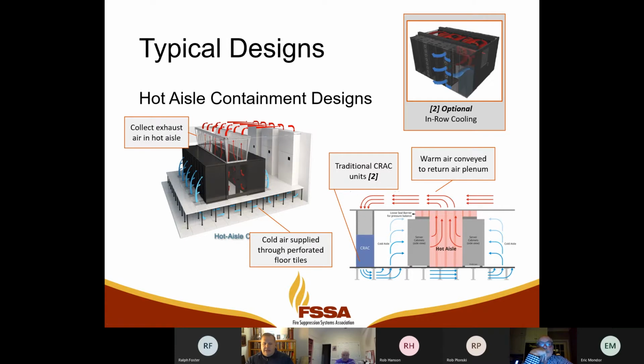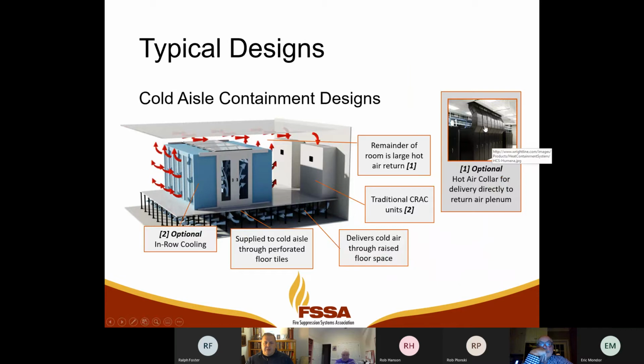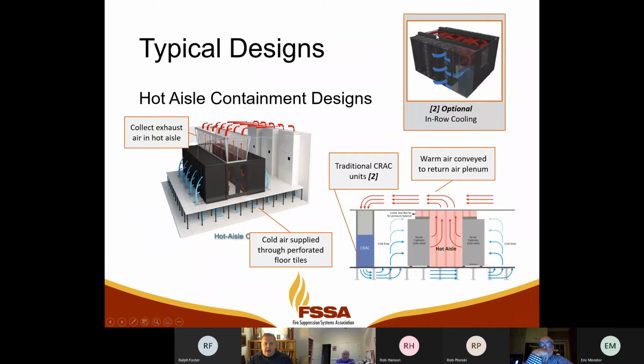There were two variants, and you'll sometimes see these in data centers. These are hot air chimneys. This is sort of a form of hot aisle containment. It's just an individual duct, more or less, from a rack to take that hot air up and out into the ceiling space. You'll see in-row cooling. It's a lot framed just like that cold aisle, with a door on each end and a roof. But then there's a cooling unit like a CRAC unit right there, taking up the space of one of the racks, and it cools air and blows cold air out, and it's drawn back in by the fan and by the little fans inside of the servers. And that's one way we recirculate the heat. So just different variations. A lot of it's doing the same thing.